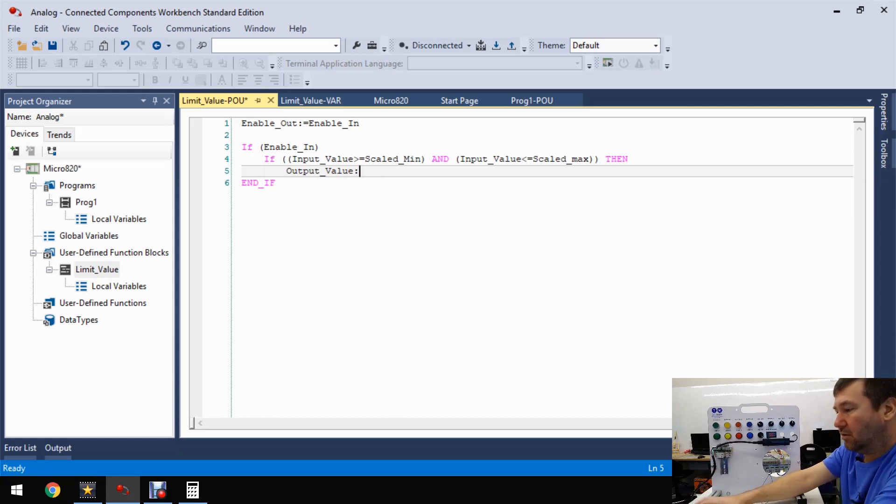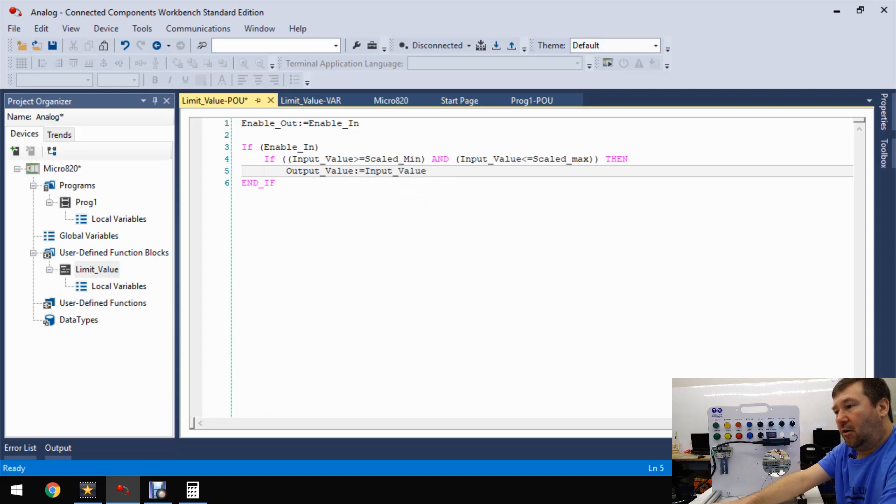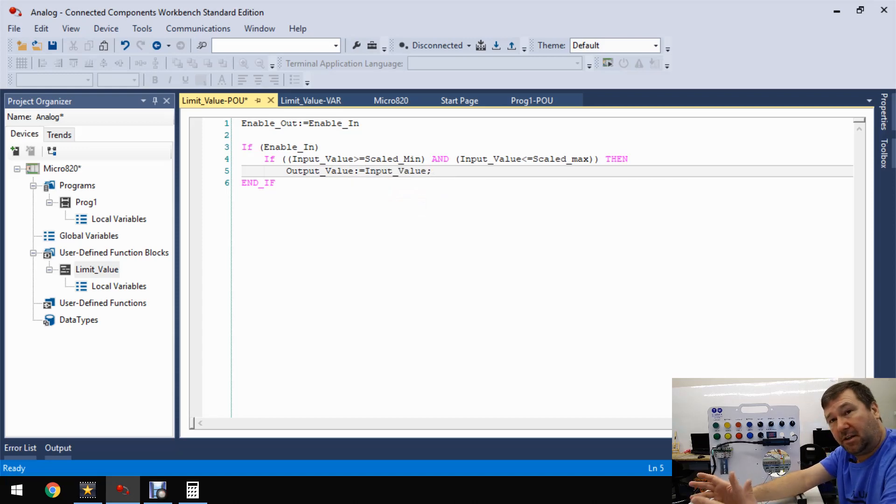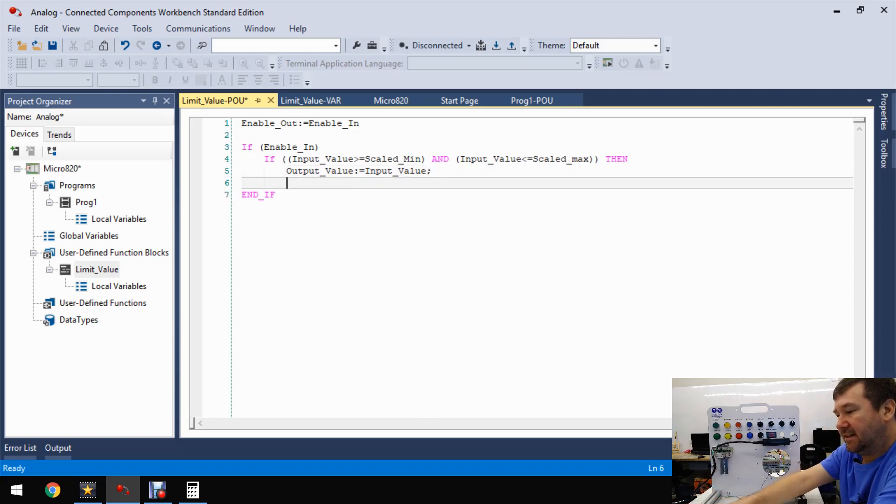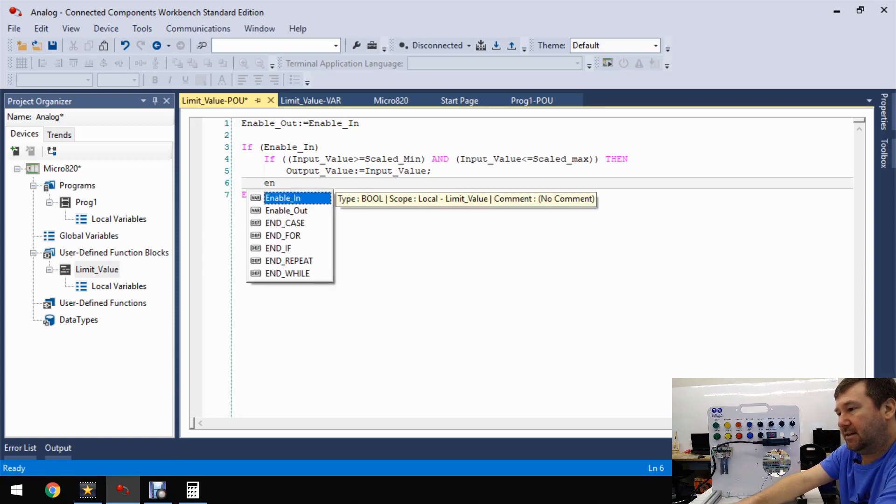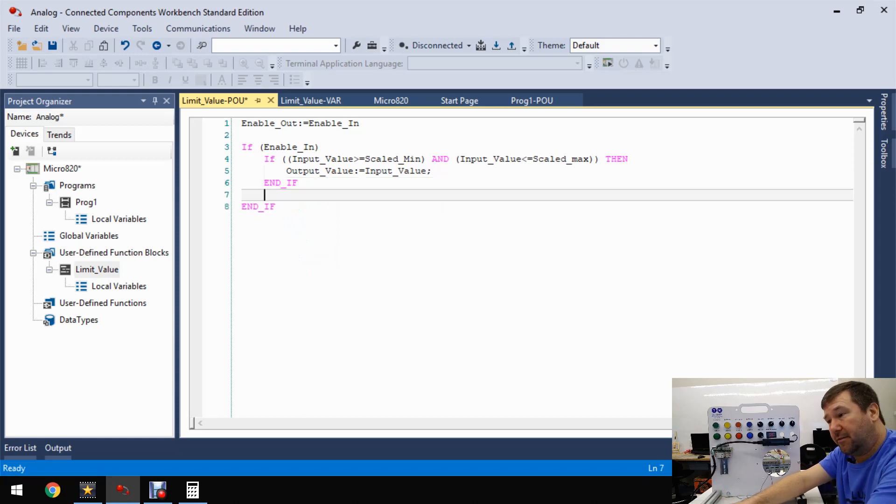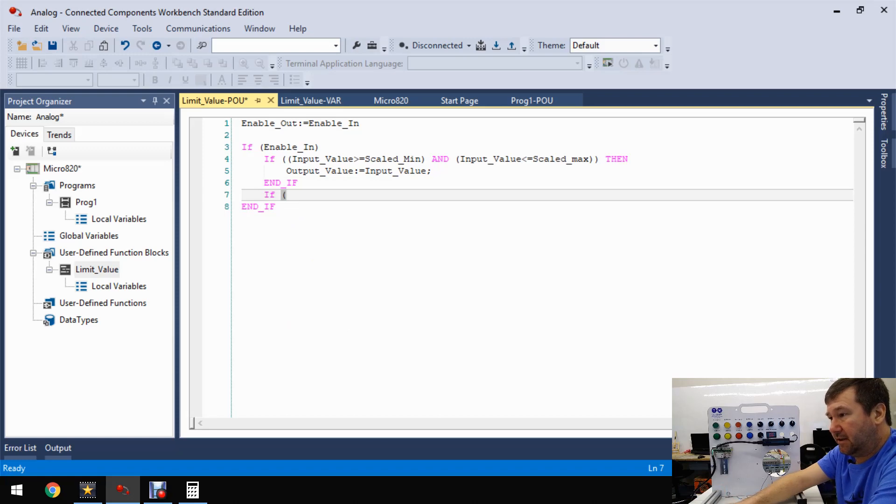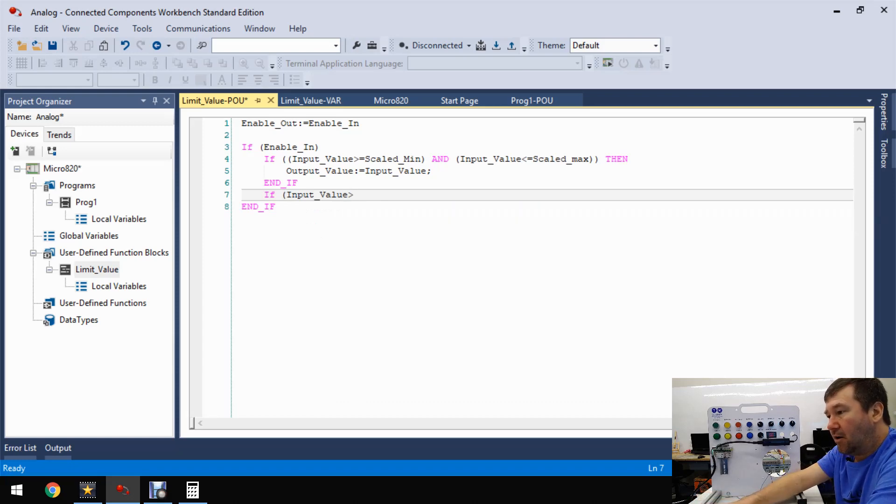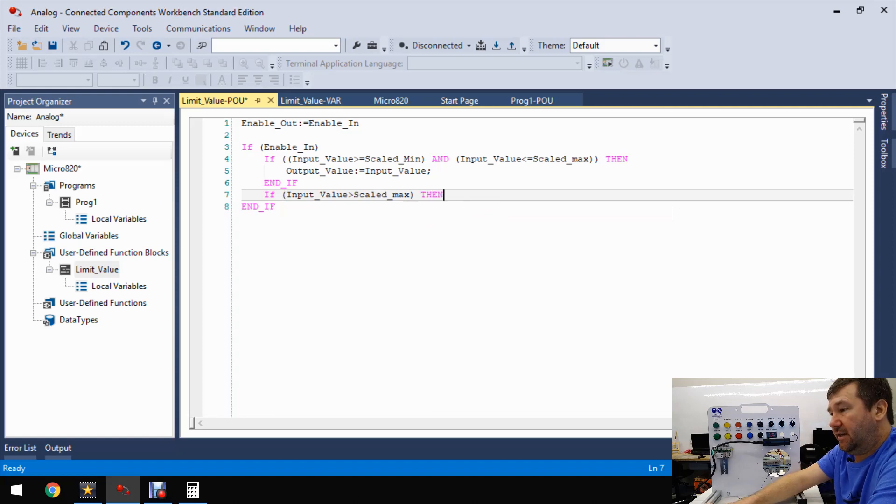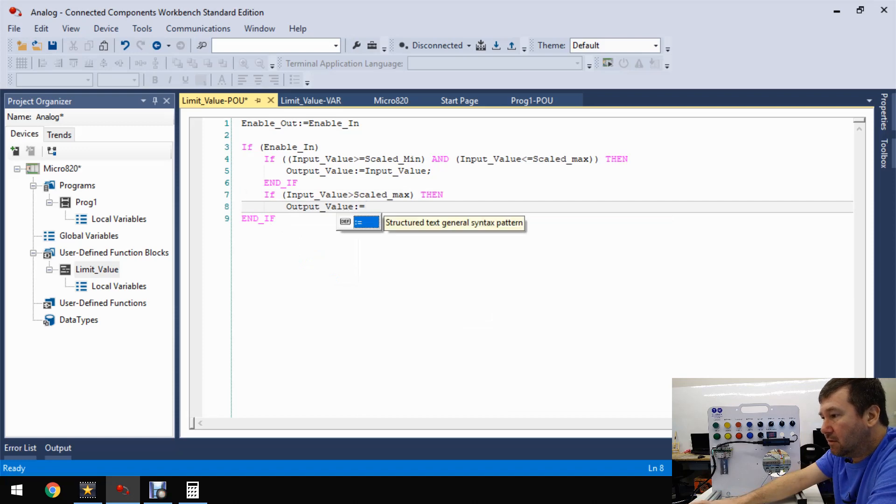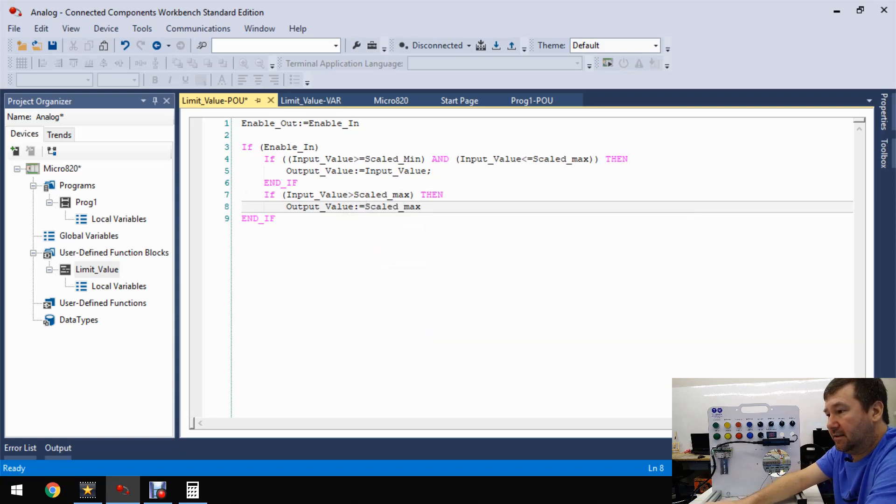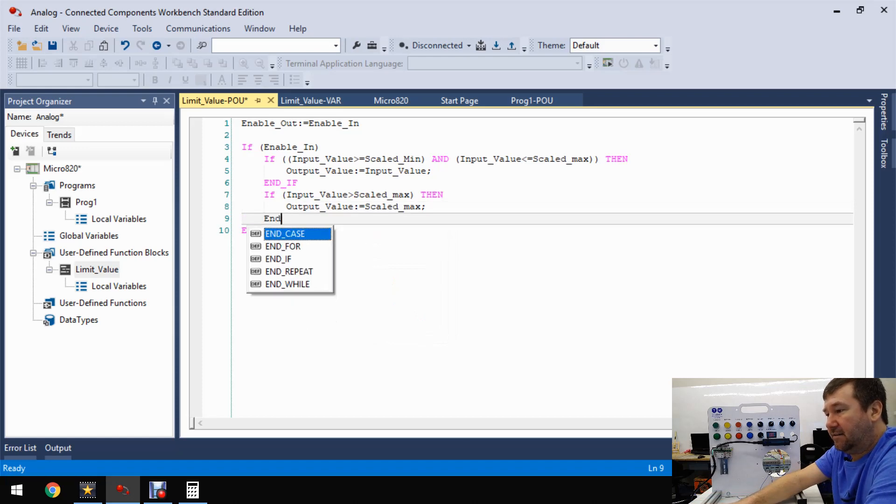So less than or equal to our scaled max, I'm going to close that one. Right over here, this should have been less than or equal to. And also, I forgot a parentheses. So that whole group here needs a parentheses. That way, it's if, and it's going to evaluate all of this. If I'd left this first group of parentheses out, it would only evaluate this part. So if both of those are true, then we're going to put a then statement. And in this case, we'll just put our output value is going to equal - well actually, it's not equal because this is a compare statement. It is going to be colon equal, which tells it to move the value.